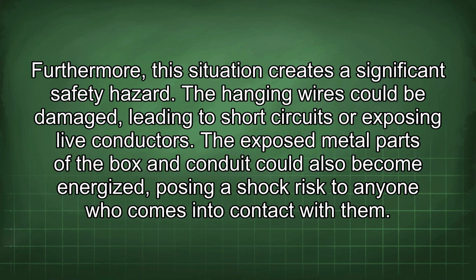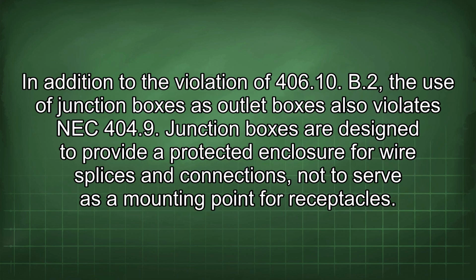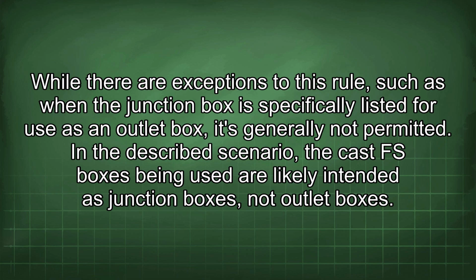Furthermore, this situation creates a significant safety hazard. The hanging wires could be damaged, leading to short circuits or exposing live conductors. The exposed metal parts of the box and conduit could also become energized, posing a shock risk to anyone who comes into contact with them. In addition to the violation of 406.10.B2, the use of junction boxes as outlet boxes also violates NEC 404.9. Junction boxes are designed to provide a protected enclosure for wire splices and connections, not to serve as a mounting point for receptacles. While there are exceptions to this rule, such as when the junction box is specifically listed for use as an outlet box, it's generally not permitted.